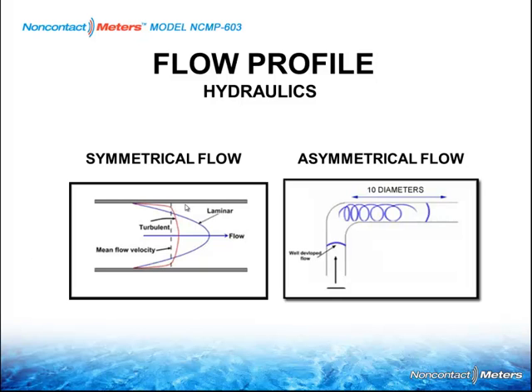Unless, in most applications, there are other applications that go higher than that flow rate, and if you had higher flow rate, you'd need more straight run of pipe. Lower the flow rate, you have less straight run of pipe. And on a symmetrical flow profile, what you're trying to achieve here, because you're between the two elbows, the flow has a chance to optimize in that it will have these elliptical shapes, faster in the center and slower near the pipe wall.